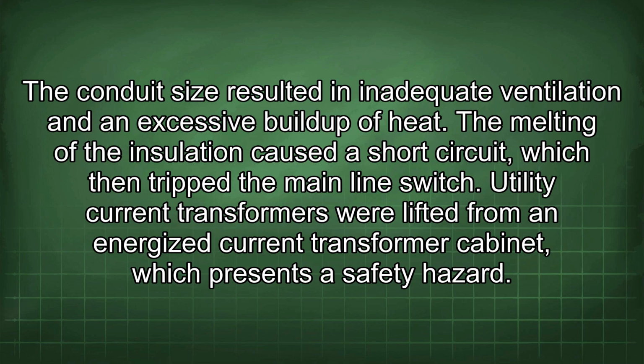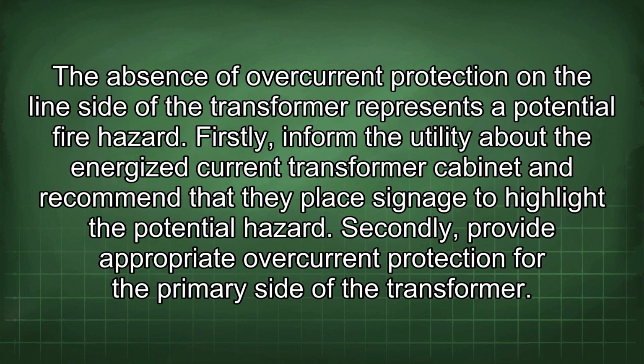Utility current transformers were lifted from an energized current transformer cabinet, which presents a safety hazard. The absence of overcurrent protection on the line side of the transformer represents a potential fire hazard. Firstly, inform the utility about the energized current transformer cabinet and recommend that they place signage to highlight the potential hazard. Secondly, provide appropriate overcurrent protection for the primary side of the transformer.